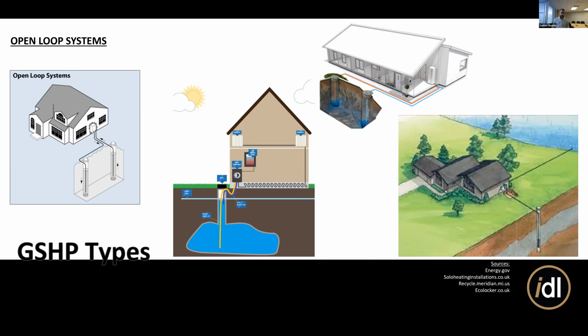However, it can have higher maintenance costs because this water initially needs to be filtered so that it can go through the heat exchanger. And even with that, sometimes the minerals can foul up the heat exchanger a little bit. So every 3 to 5 years, you might need to run a decalcifying agent through the heat exchanger so it doesn't clog up. I believe that was the issue here in the building where I am right now, where it was initially an open loop system, and it ended up not turning out for the best.